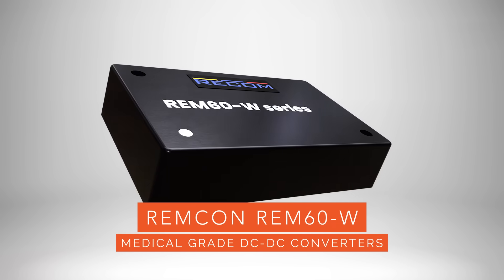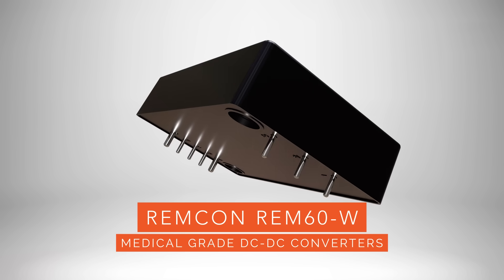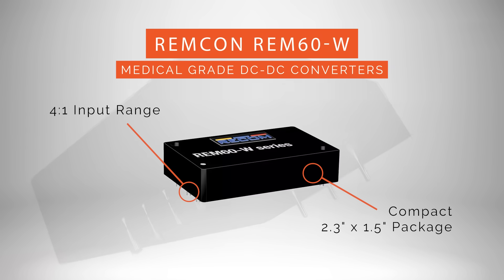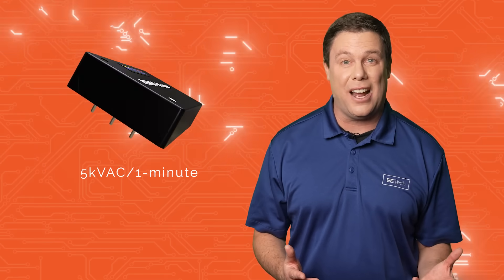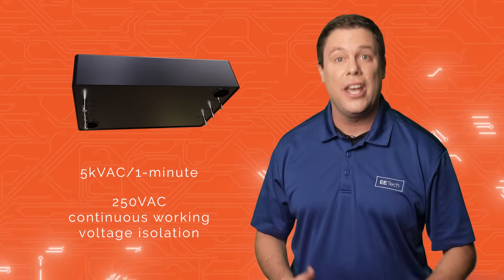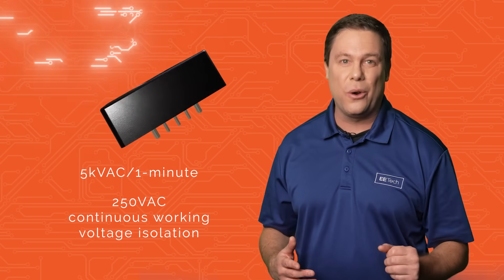RECOM's REM60W medical-grade DC to DC converters are efficient devices delivering a reliable 60-watt power output. With a 4-to-1 input range and housed in a compact 2.3-inch by 1.5-inch package, these converters adhere to stringent medical-grade standards. They also feature reinforced 5 kilovolts AC per 1-minute isolation, ensuring safety with 250 volts AC continuous working voltage isolation. They provide consistent single and dual outputs even at zero load.